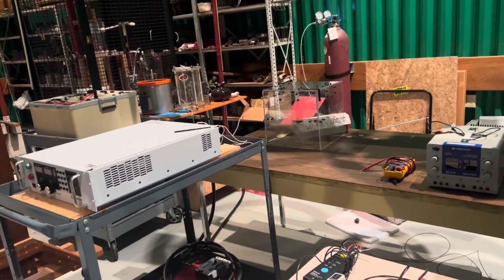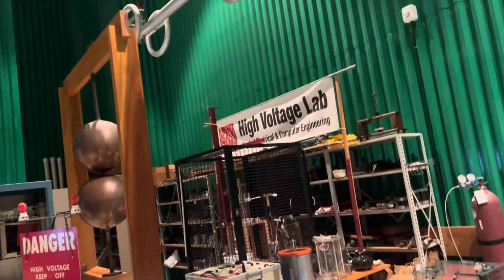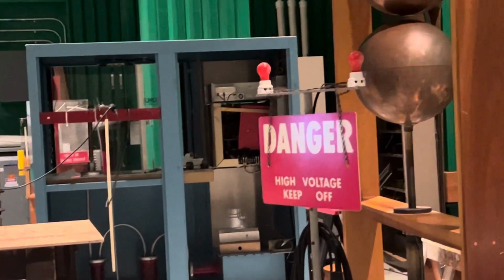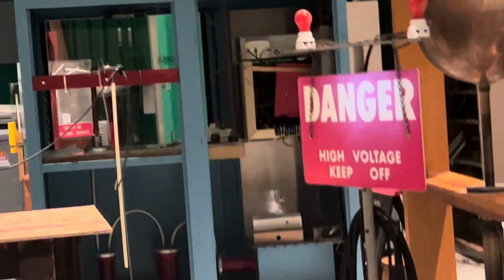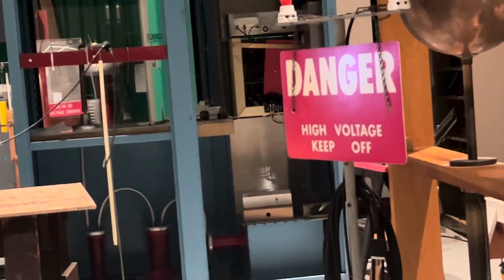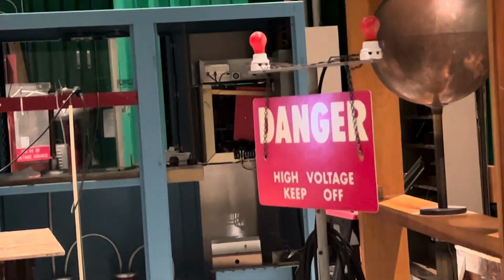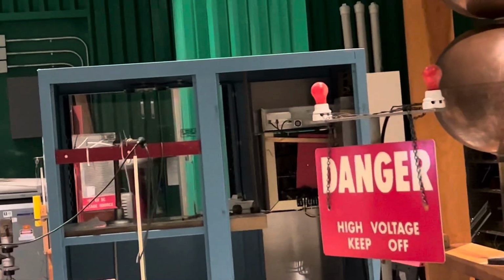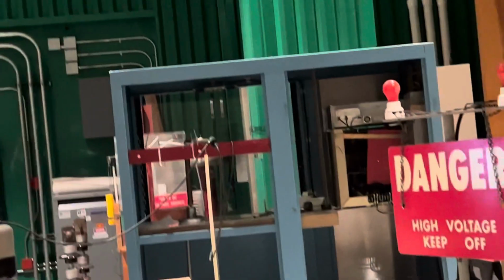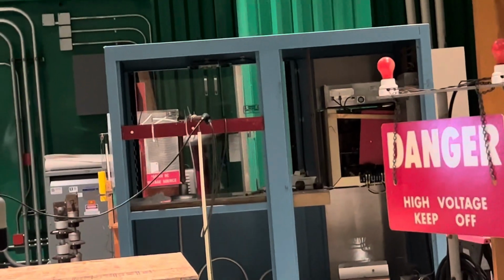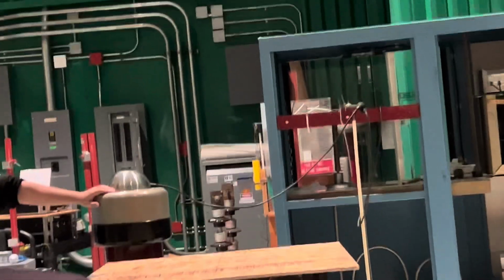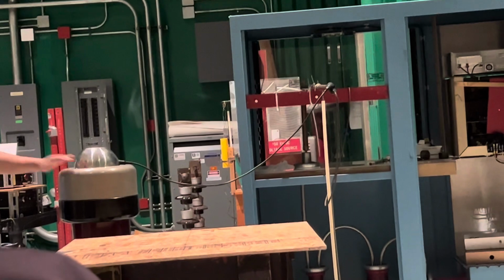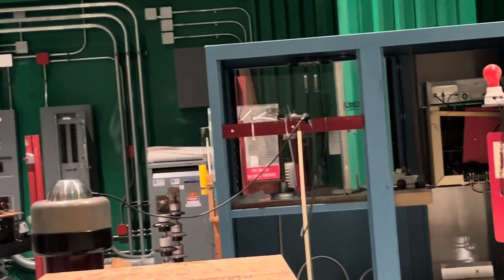Here we use this setup to do the 60 Hz AC test. This blue one is the source. It can generate a sinusoidal AC waveform up to 50 kilovolts. With this high voltage level, we cannot easily find a proper probe to detect the applied voltage, so we use this capacitive voltage divider. It can divide the applied voltage to a lower value so it can be monitored by the equipment.